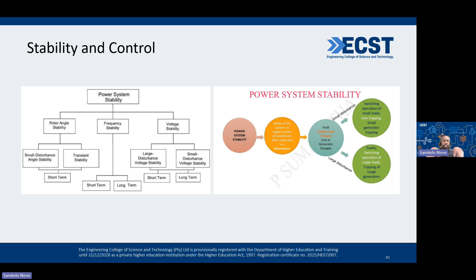So everything, like generators and transformers, the whole system is synchronized to operate at 50 hertz. It can go up or down by plus or minus 0.5 hertz, or if you're stricter, plus or minus 0.2 hertz. So that's 49.5 or 49.8 to 50.2 or 50.5 hertz. Once it goes beyond or below those limits, it has to trigger the protection system, or circuit breakers, to isolate that space.